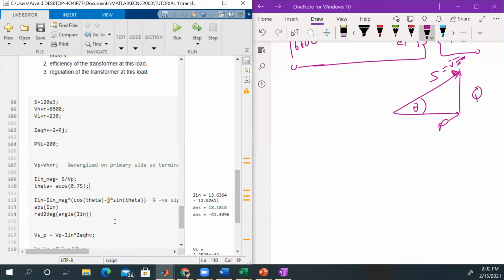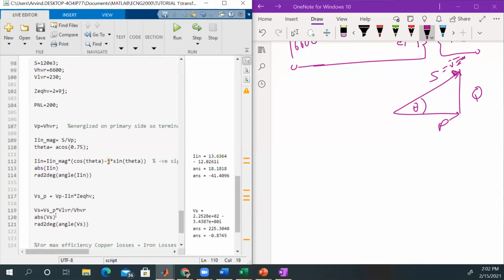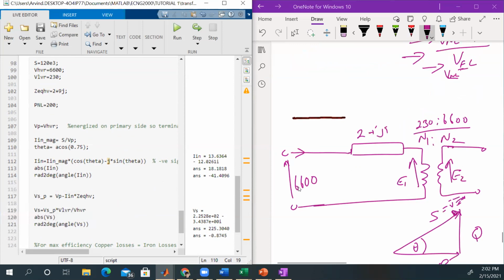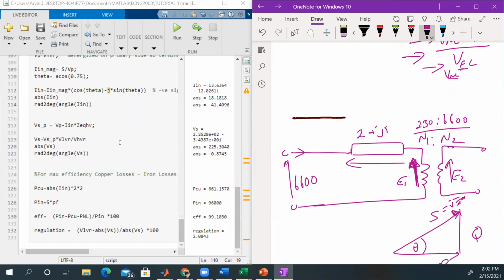So we calculate this I_in. Then V secondary equals VP minus I_in times Z equivalent on the high voltage side. This gives V secondary referred to the primary side, calculating the voltage drop and getting this value. To get the voltage referred to the secondary side, I just convert it using the turns ratio.